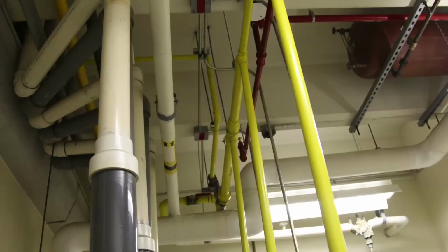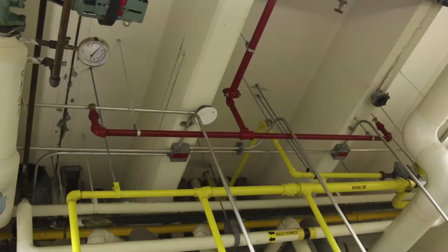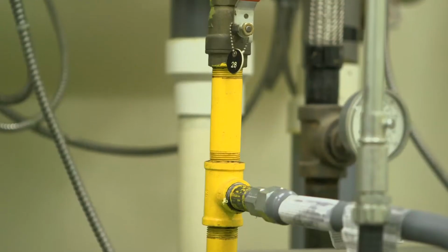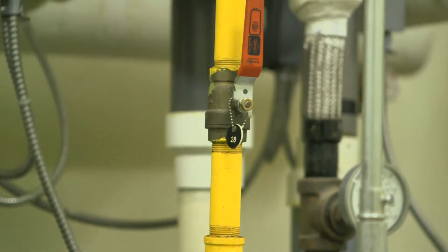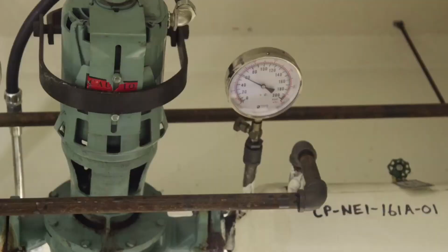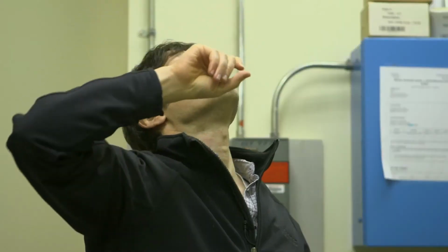Another thing that you may want to consider in all cases is to look at the piping configuration and understand how the heating plant is tied into the main hot water supply of the building. In this case, we know that these boilers are only running in the summer, so they're probably going to be using the pump above here. Can you see the pump? This is basically the boiler pump. In this case, it circulates the water through the boilers.